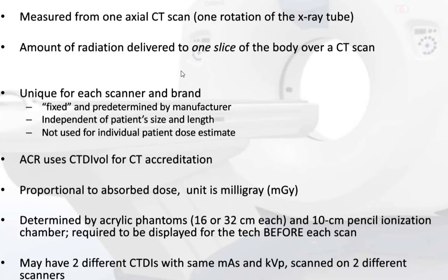CTDI volume is independent of patient size and length, and this is the main difference from DLP dose length product, which factors patient length. CTDI is not used for individual patient dose estimates. ACR uses CTDI volume for CT accreditation. It is proportional to absorbed dose, units are milligray, and it is determined by acrylic phantoms — a 16 cm or 32 cm phantom with a 10 cm pencil ionization chamber.